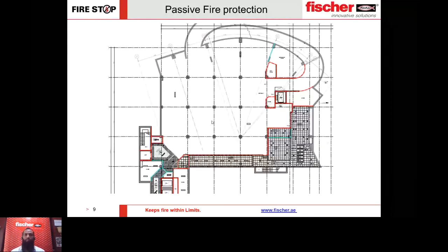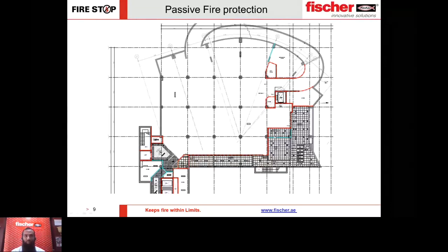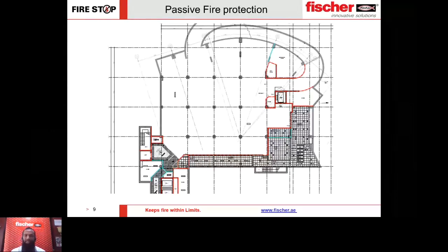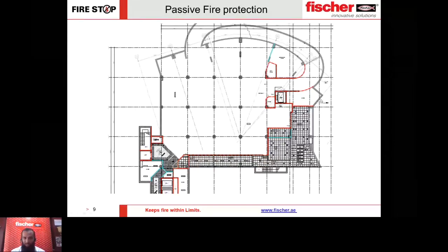If plan A fails, you always need a plan B. That plan B is also part of the fire protection strategy — something called passive systems. We divide the building into different zones separated by fire barriers. Passive fire protection means that if there is a fire in one zone, these fire barriers prevent flame, smoke, and toxic gases from passing into other zones. This is passive fire protection.